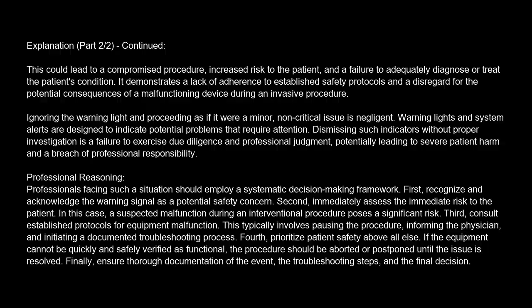Professional reasoning. Professionals facing such a situation should employ a systematic decision-making framework. First, recognize and acknowledge the warning signal as a potential safety concern. Second, immediately assess the immediate risk to the patient. In this case, a suspected malfunction during an interventional procedure poses a significant risk. Third, consult established protocols for equipment malfunction. This typically involves pausing the procedure, informing the physician, and initiating a documented troubleshooting process. Fourth, prioritize patient safety above all else. If the equipment cannot be quickly and safely verified as functional, the procedure should be aborted or postponed until the issue is resolved. Finally, ensure thorough documentation of the event, the troubleshooting steps, and the final decision.